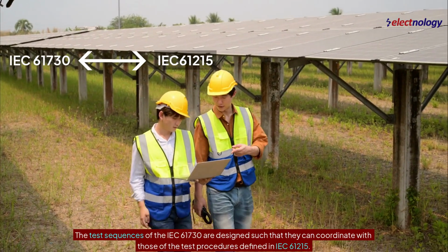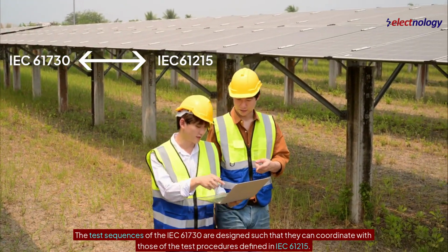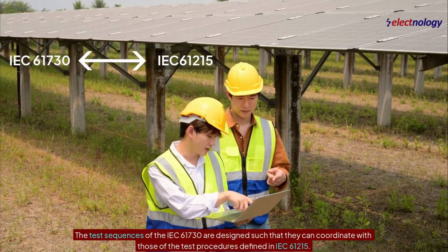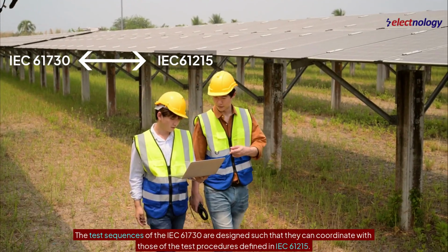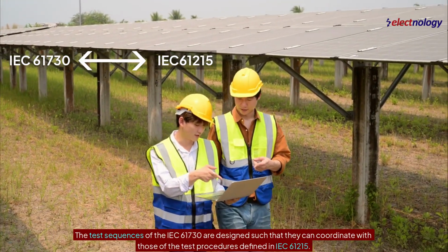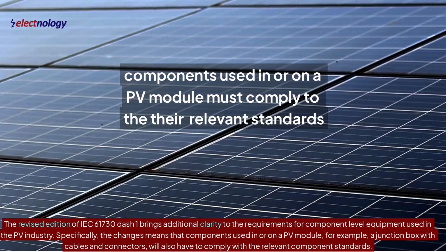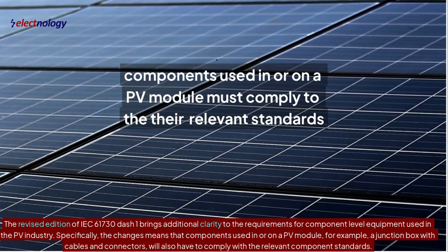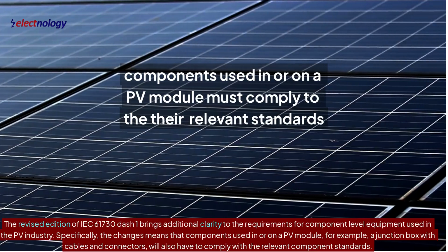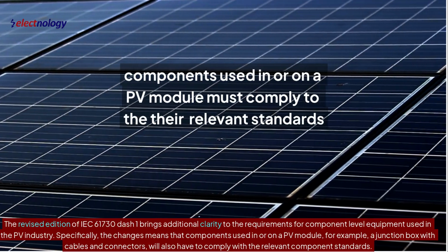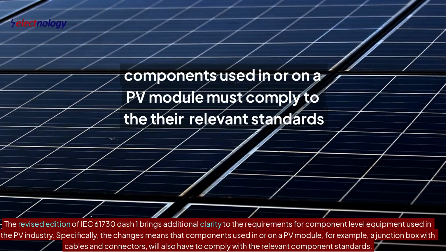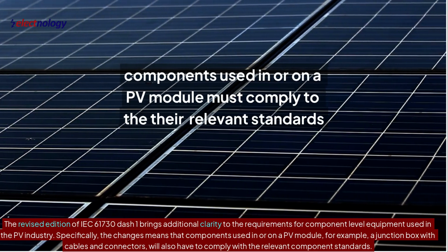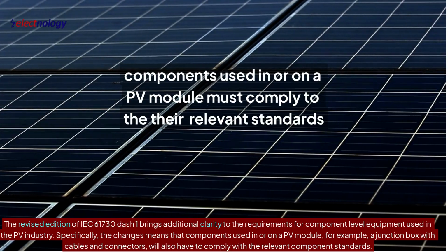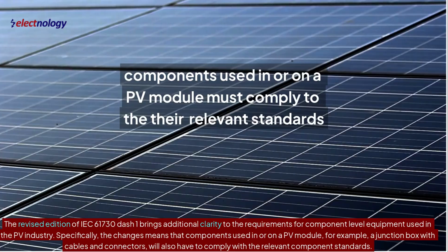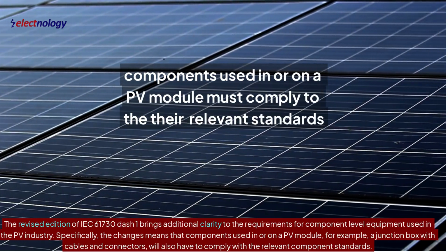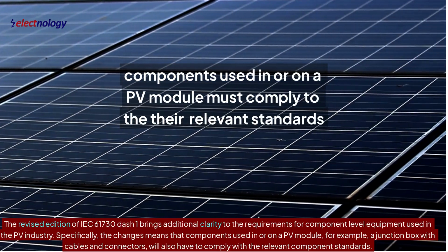The test sequences of the IEC 61730 are designed such that they can coordinate with those of the test procedures defined in IEC 61215. The revised edition of IEC 61730-1 brings additional clarity to the requirements for component-level equipment used in the PV industry. Specifically, the changes mean that components used in or on a PV module, for example, a junction box with cables and connectors, will also have to comply with the relevant component standards.